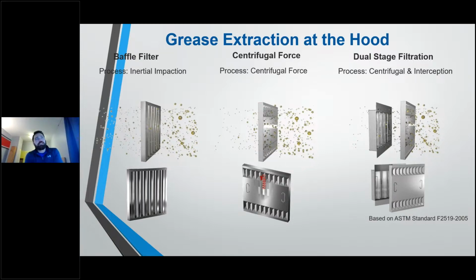The final grease filtration that you'll see in the market, but it's very rarely used, would be some sort of dual stage filtration. These are going to be almost 100% efficient, but they're going to be extremely costly. And they add a ton of static pressure to a system, which increases the size of your fans and the costs associated with it. Everybody does these slightly differently, but these three stages of filtration are generally seen across the industry. And that middle stage, the centrifugal force, is definitely the most popular one that we are seeing, again, across all disciplines in the industry.